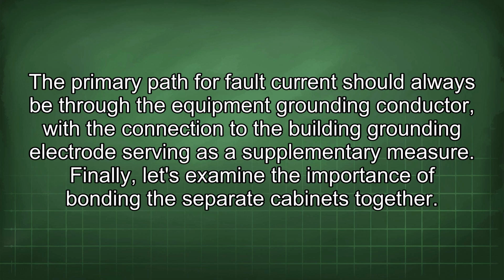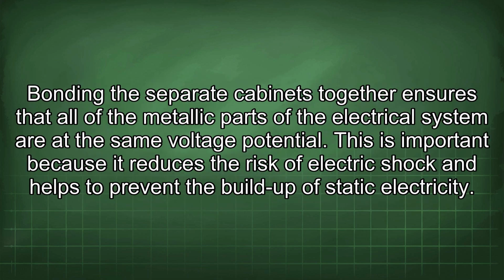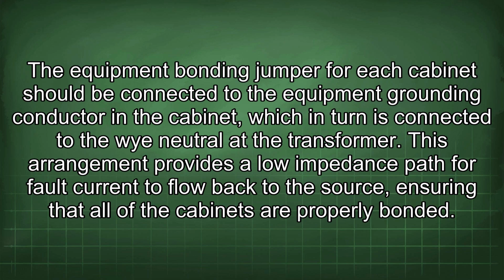Finally, let's examine the importance of bonding the separate cabinets together. Bonding the separate cabinets together ensures that all of the metallic parts of the electrical system are at the same voltage potential. This is important because it reduces the risk of electric shock and helps to prevent the buildup of static electricity. The equipment bonding jumper for each cabinet should be connected to the equipment grounding conductor in the cabinet, which in turn is connected to the wye neutral at the transformer. This arrangement provides a low impedance path for fault current to flow back to the source, ensuring that all of the cabinets are properly bonded.